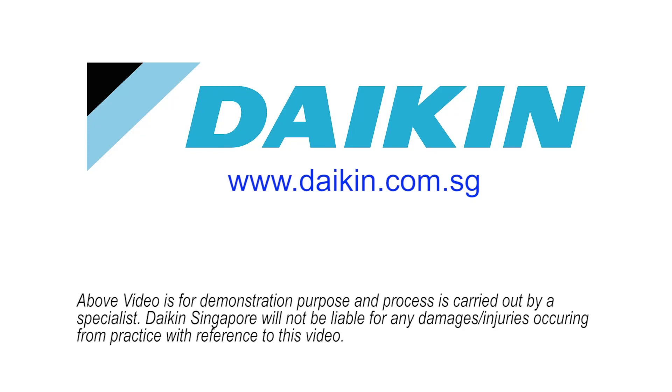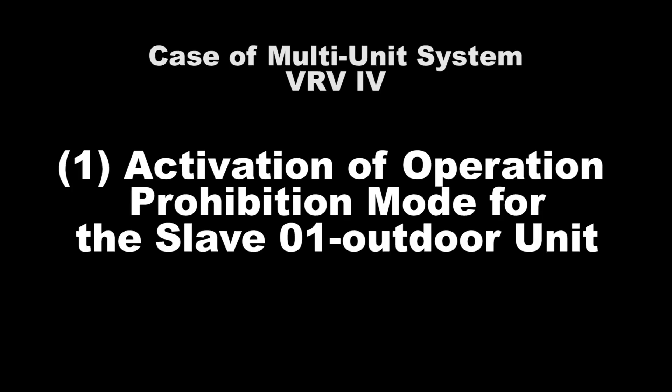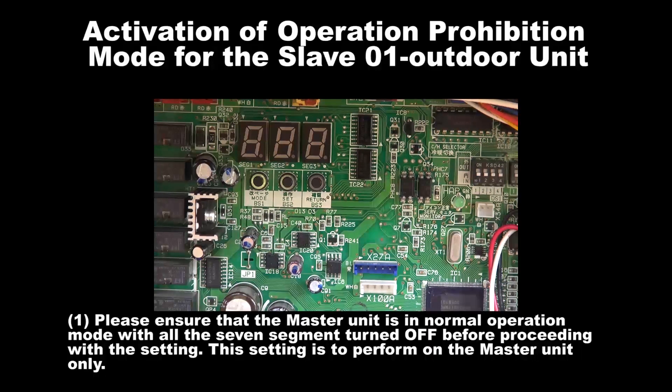In this video, we will show the setting for VRV4 Slave 1 Unit Operation Prohibition Mode in the Master Outdoor Unit. Number 1: Activation of Operation Prohibition Mode for Slave 1 Unit. Step 1: Please ensure that the master unit is in normal operation mode with all the 7 segments turned off before proceeding with the setting. The setting is to be performed on the master unit only.